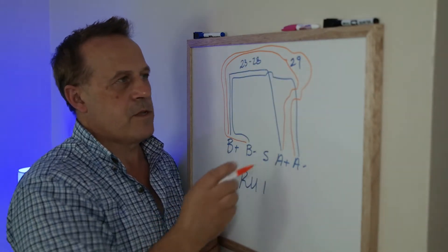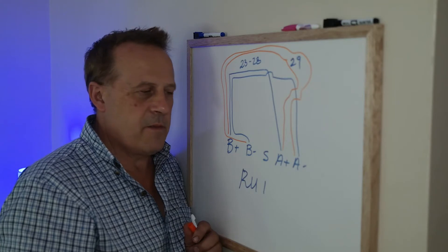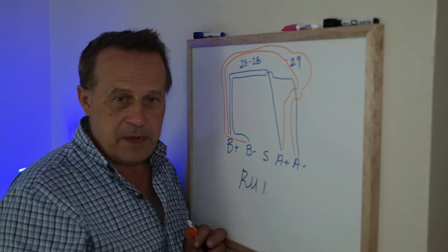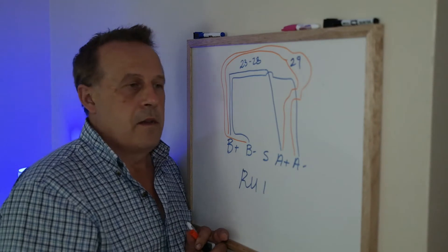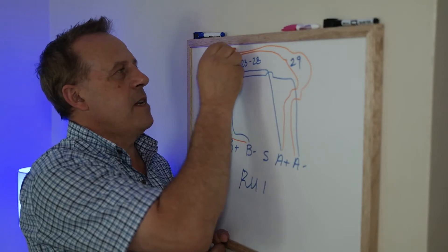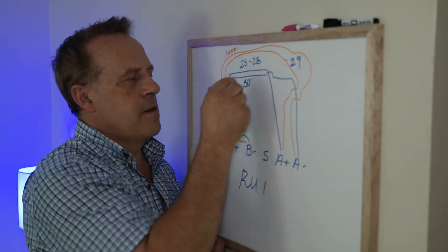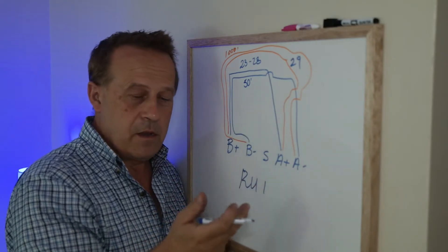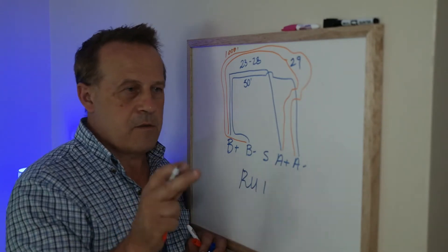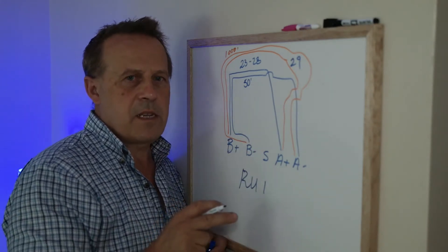So you had what was a double class A loop, which is like trying to drive two cars at the same time. It just doesn't work that way. I had this question way back when I taught this course at the IBEW. He asked me, why not have a redundant loop? You don't do that. What if this one is a thousand feet and this one is 50 feet? Do you see where I'm going? There's going to be some reflection there, some electrical interference due to reflection. One signal taking longer than the other. It's a nightmare. Obviously people are thinking about this because it's being done.